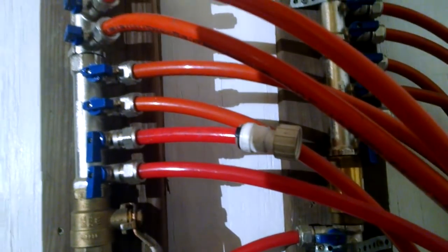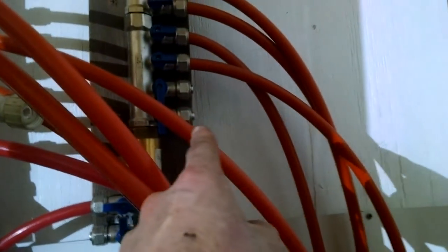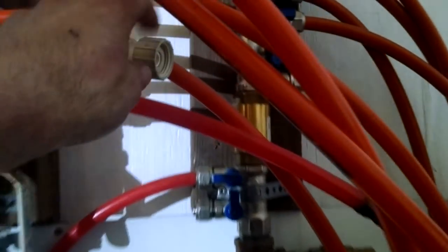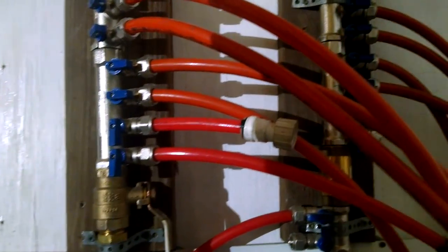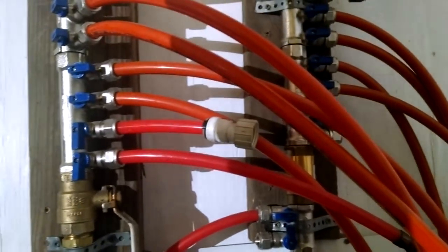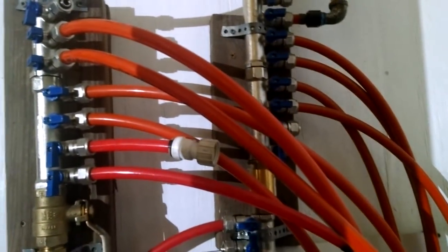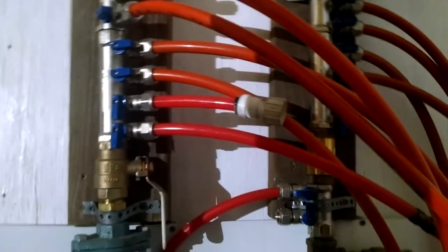Here we have one outlet that's just a purge line, and this one here is for cleaning of the system. The system builds up scale over time, and we can circulate by using this and another outlet on another side here. This is an easy, quick connect with just a hose coupling, so we can basically close the loop around the heat exchanger and circulate vinegar, and that will descale your system. You want to descale it every so often so that you get better heat exchange.